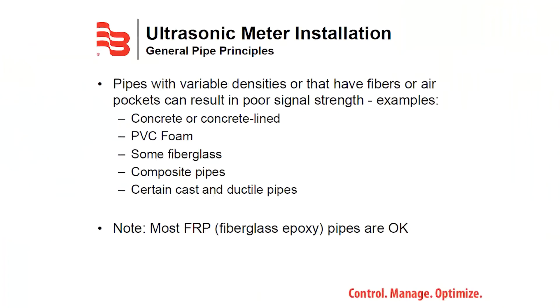Pipes with variable densities or that have fibers or air pockets can result in poor signal strength. Examples include concrete or concrete-lined, PVC foam, some fiberglass composite pipes, and certain cast and ductile pipes. Note: most FRP pipes are okay.